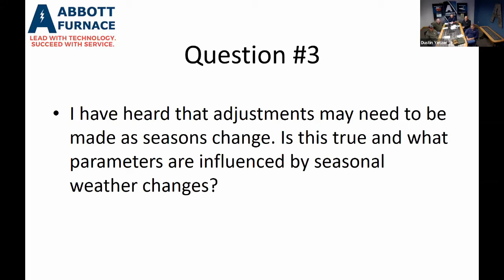Yes, that is true. I can see we have some guys in the local area and north here asking questions. Generally up here, we do have pretty dramatic seasonal changes between warm and cold. We do see issues in the furnaces and in the buildings. What that's attributed to is the atmosphere in the furnace. We have to have a positive pressure in that atmosphere, so we want that atmosphere pushing out the front door and the rear doors of the furnaces.